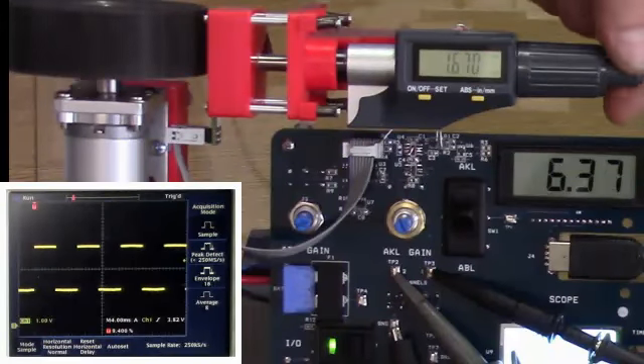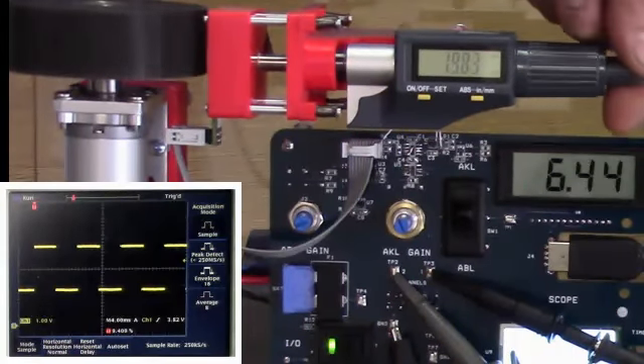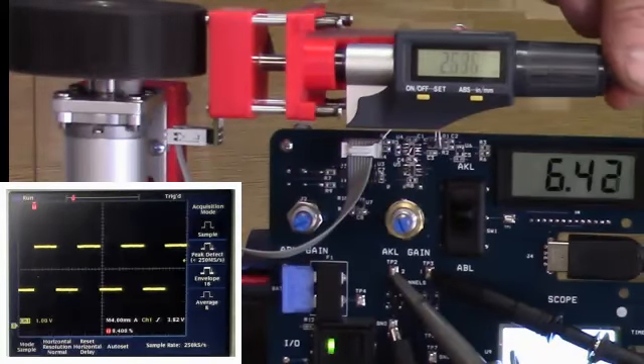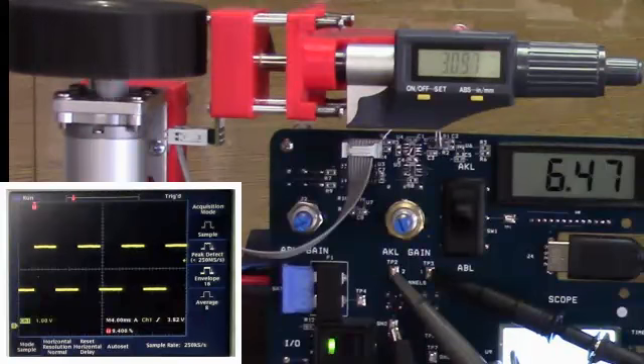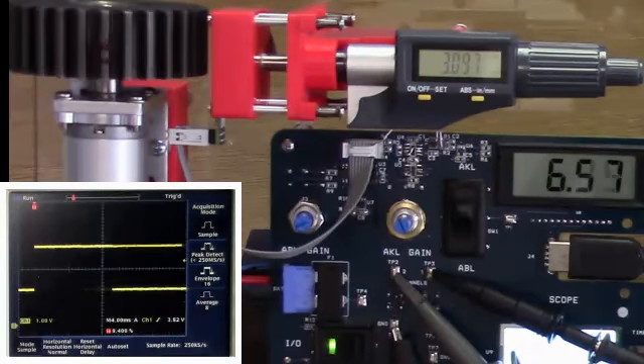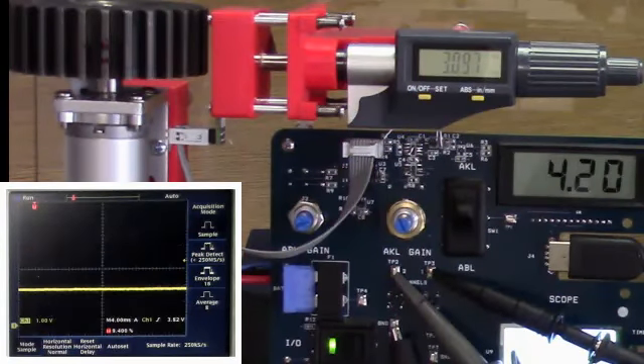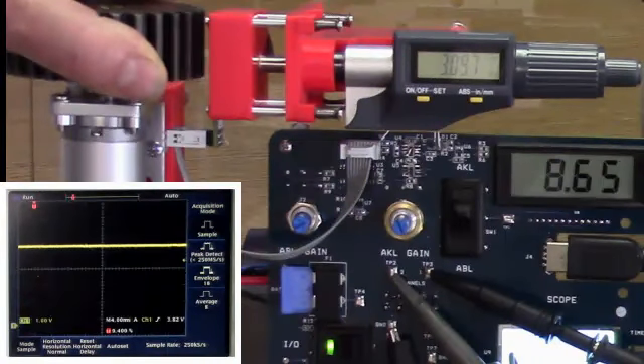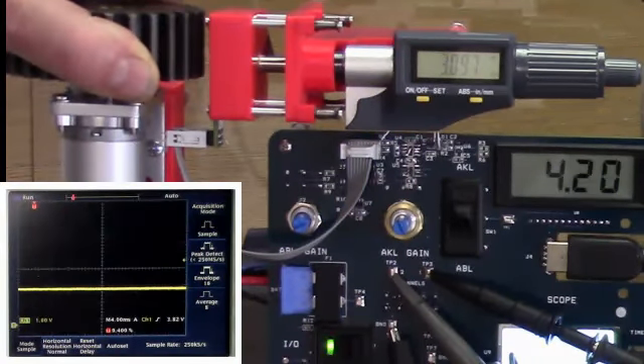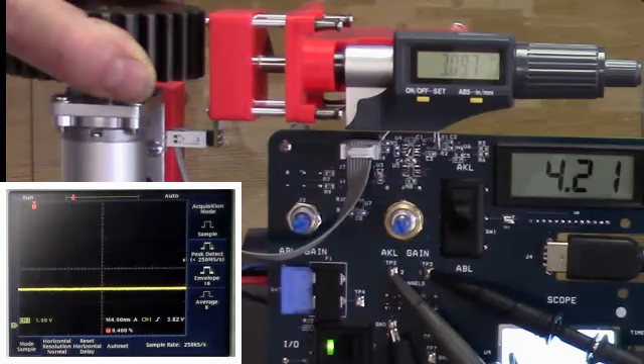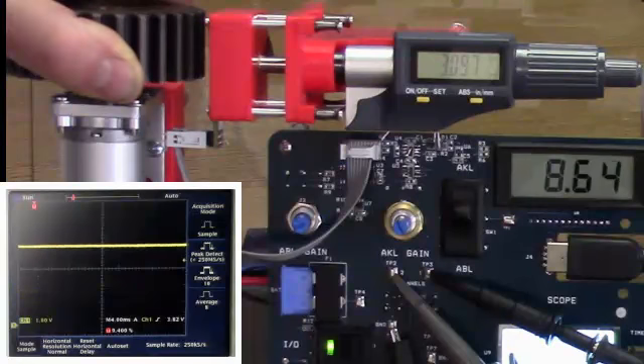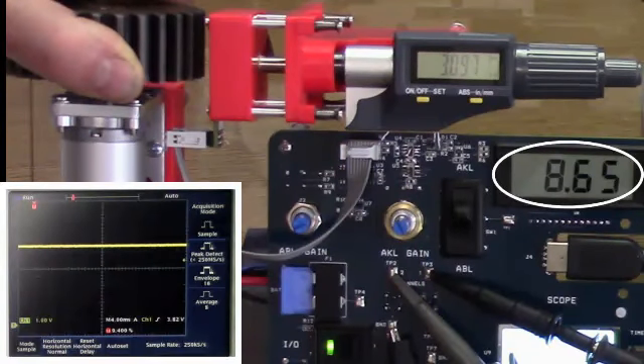As I change the air gap the output doesn't change. And if I turn the gear slowly by hand you see the sensors work to zero speed or DC. This is a current modulated two-wire device. The current switches between four milliamps and eight milliamps to indicate a gear tooth.